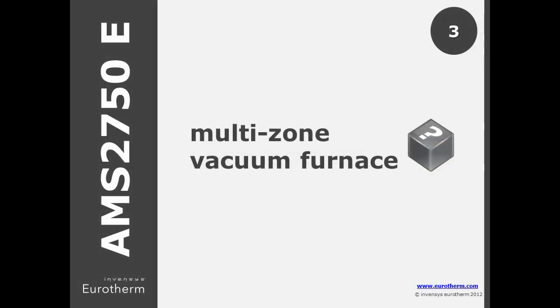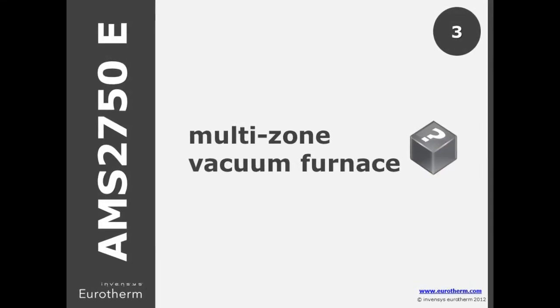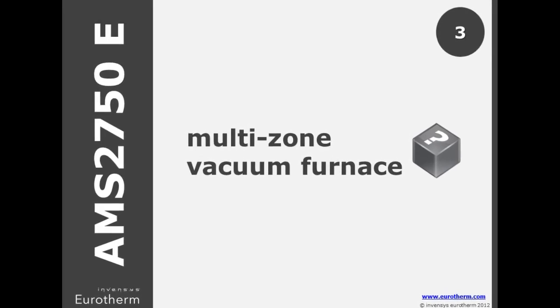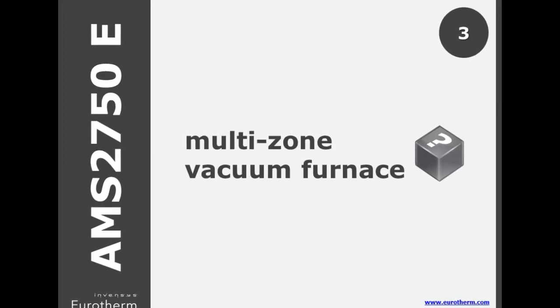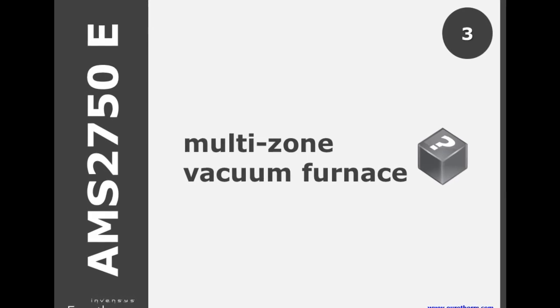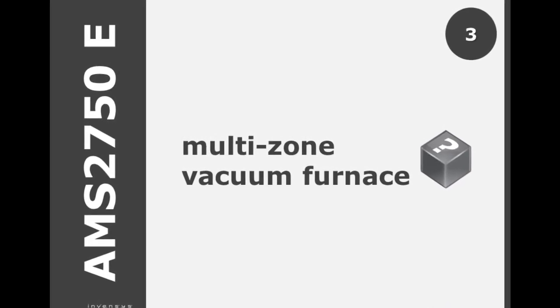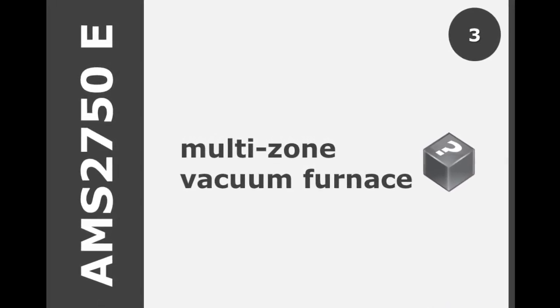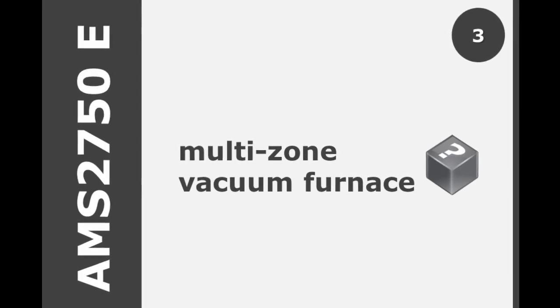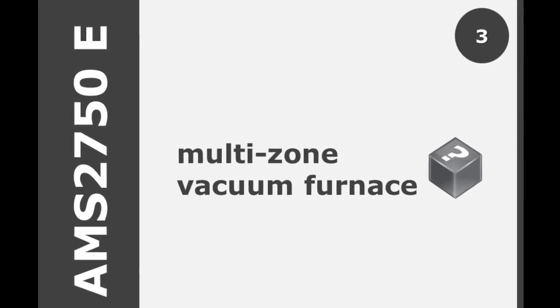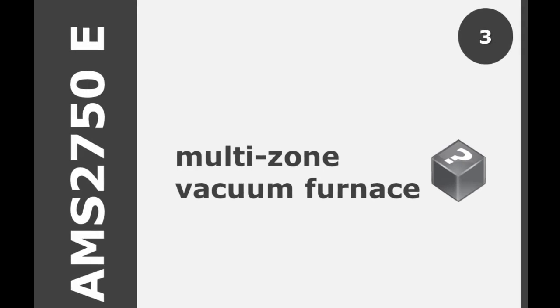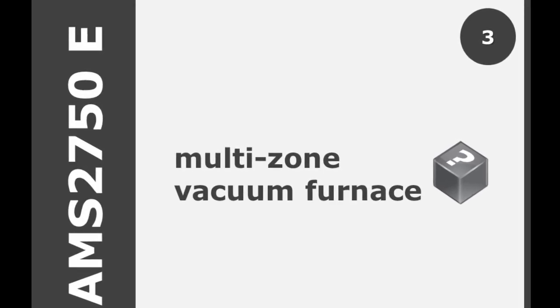Using instrument types A or C in a vacuum furnace, the D standard outlined each control zone with a dedicated control thermocouple needed high, low and load sensors. In E, rather than for each control zone, you can split the entire working volume into 225 cubic foot zones and can treat each of these zones as a single control zone to determine the overall number of high, low and load sensors.